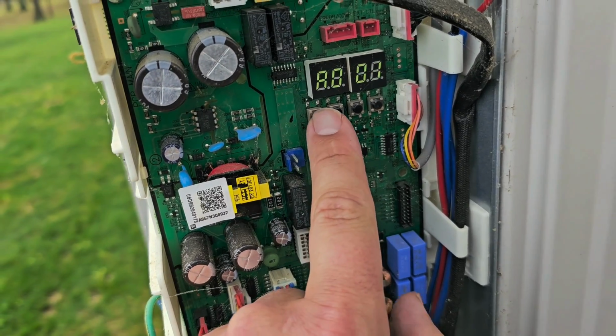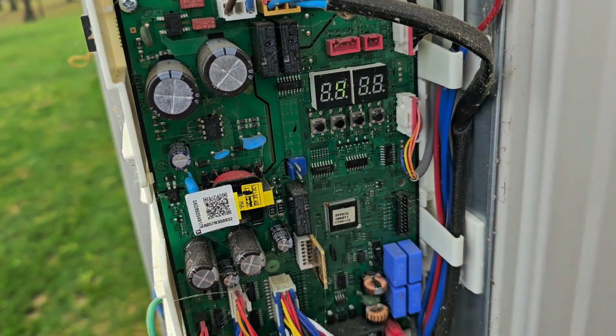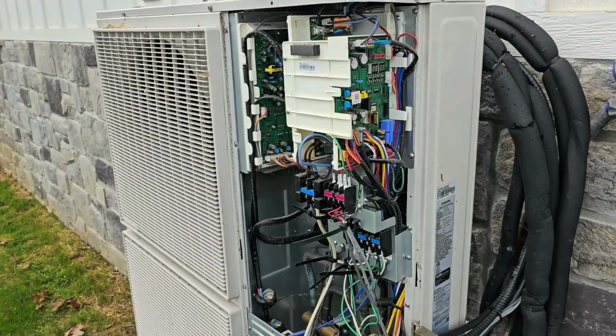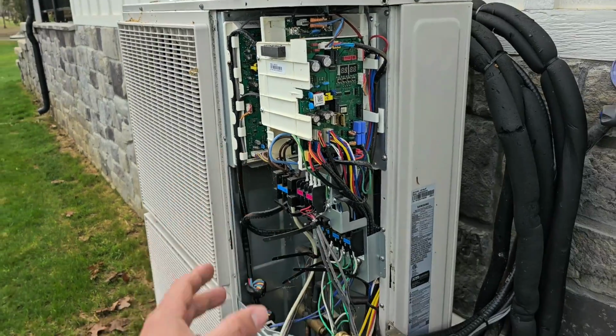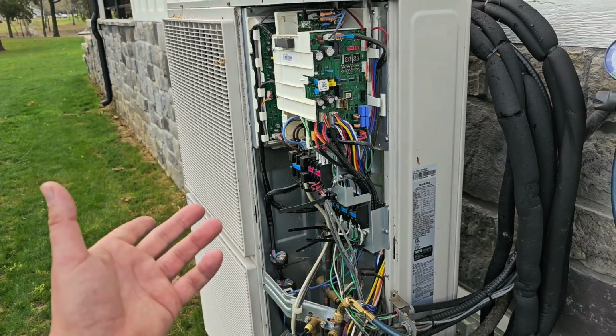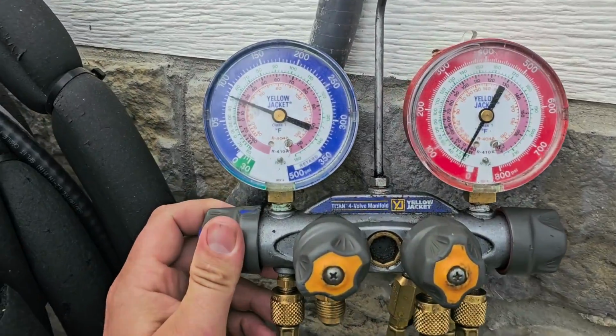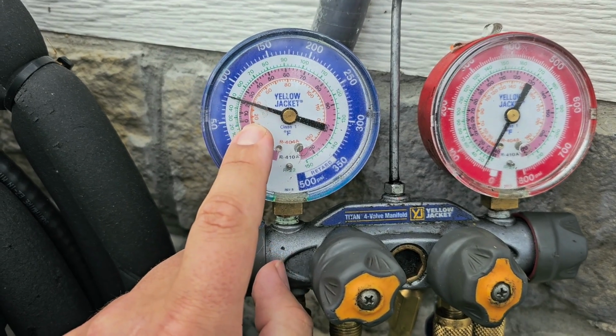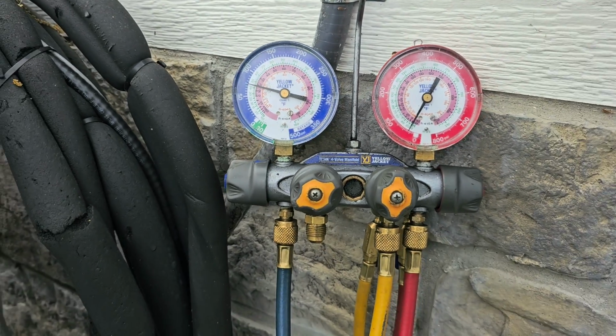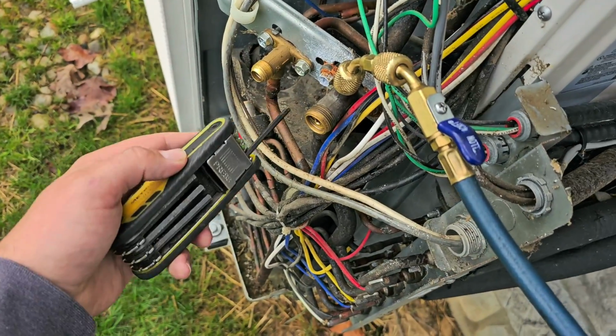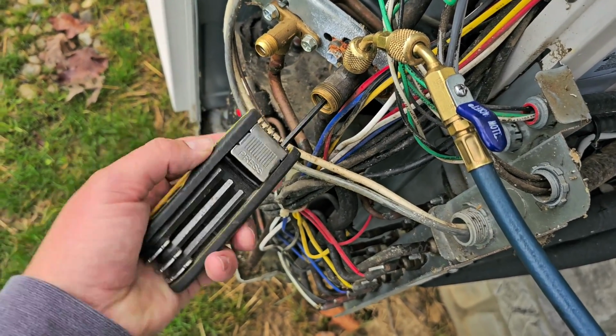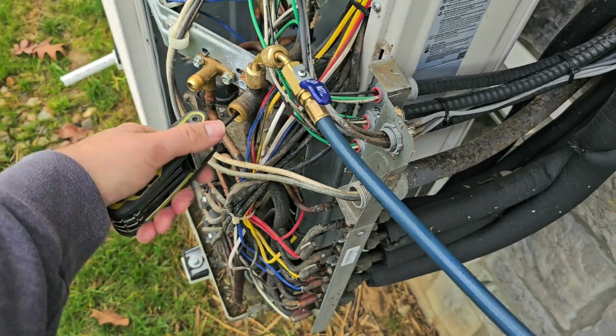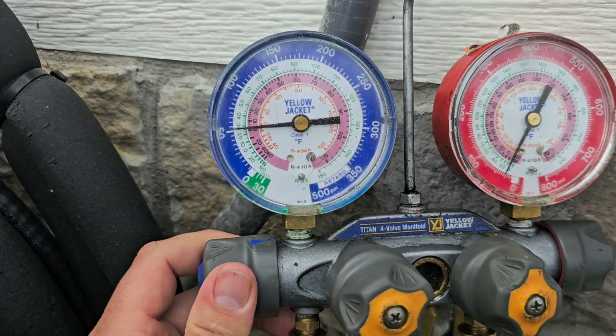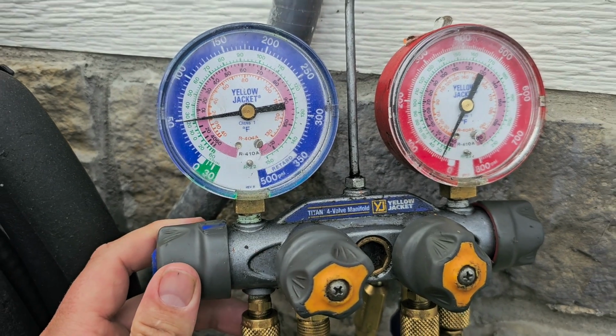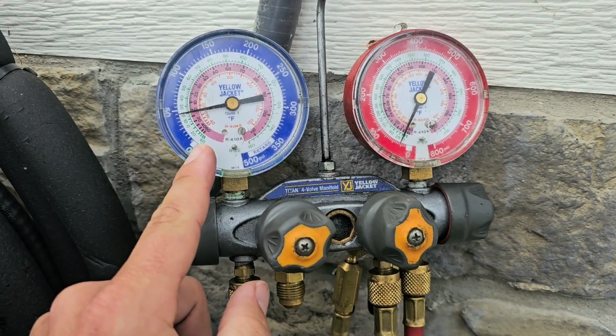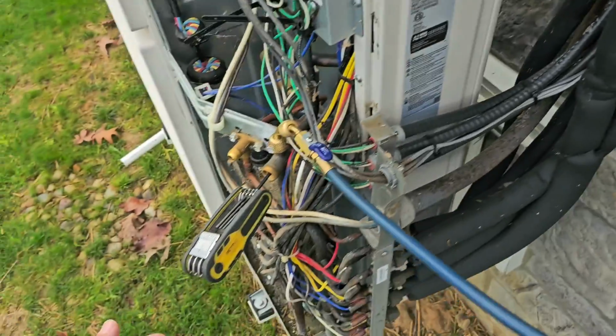We're going to push the K1 button 1, 2, 3, 4 times. Now we're in pump down operation. Equipment is on and running. It did take a minute or 2 for it to turn on, and you can see what's happening. Low side pressure is dropping. So I'm going to take the Allen tool and move it to the suction line service valve. Make sure that I can turn it, and looks like we're at 50. I'm going to wait till we're at 0, and then we're going to close the valve.